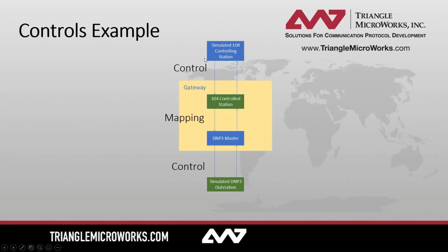This is what we're going to be creating. We have a controlling station, that's a 104, which is going to issue a control down to the gateway. It's the gateway's job to get that control and send it out to a DNP3 outstation. So, like we've done with mapping when data was moving upstream, we're going to put a 104 controlled station inside the gateway's database, and push that down to a DNP3 master.